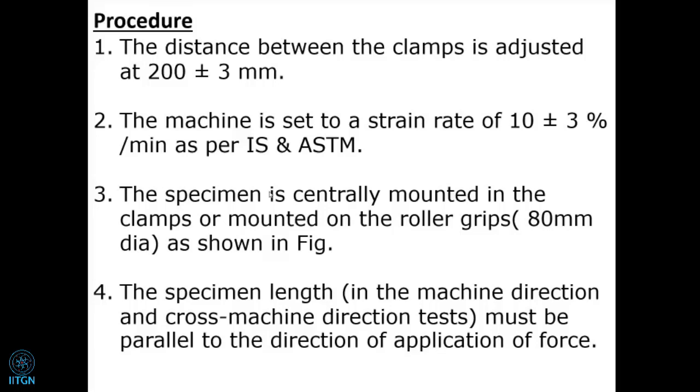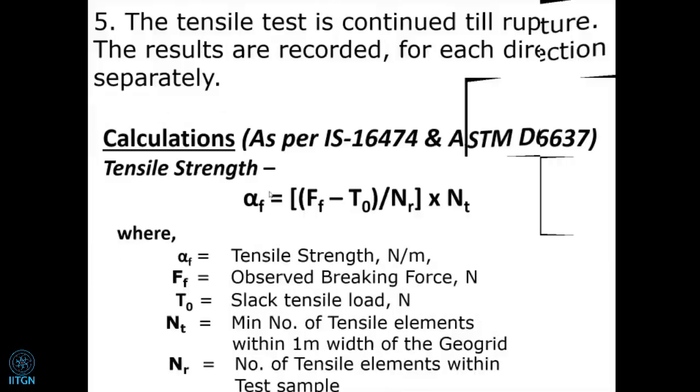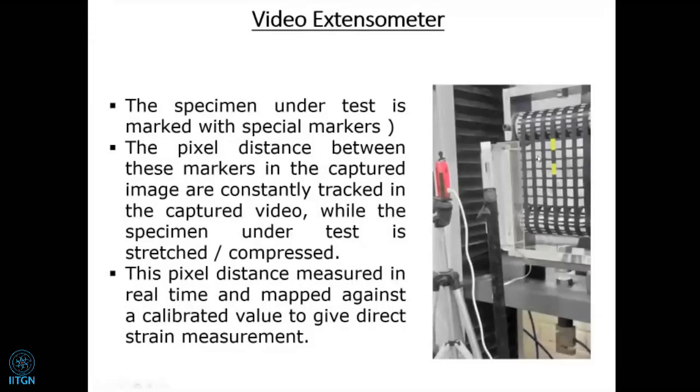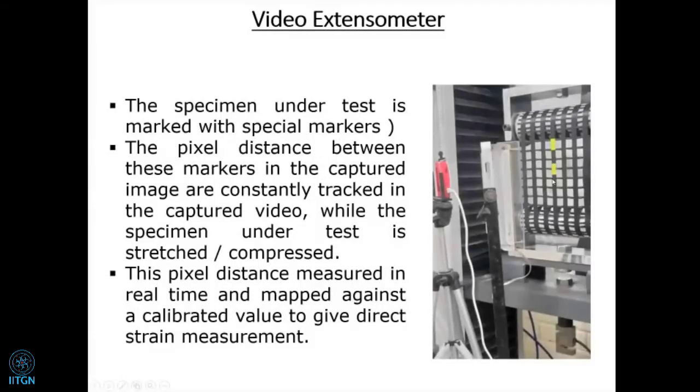Then the specimen length in the machine direction and cross machine direction must be parallel to the direction of the application of forces, like this. This is the sample, and the vertical direction is parallel to the direction of the tensile force applied on this sample.